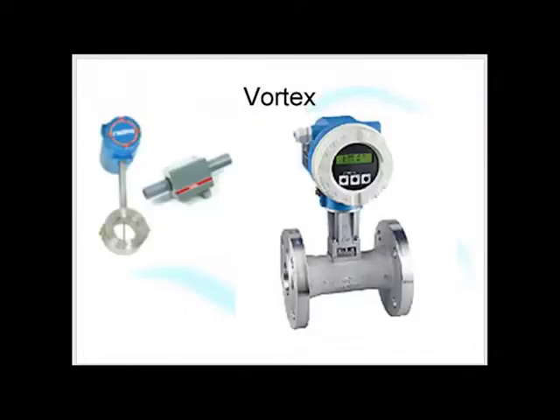Now, this is what vortex flow meters look like, they tend to be very, very solid. We use these for measuring things that we can't easily measure other ways. Basically nasties, and real nasties. Things like steam. Steam, superheated steam or saturated steam, is very, very nasty. It's very unpleasant and it tends to damage flow meters. The vortex flow meter will happily measure saturated steam.